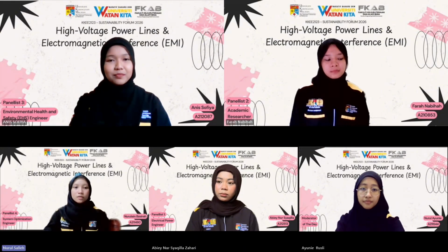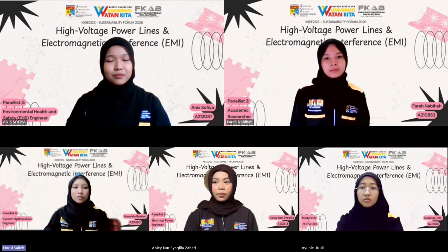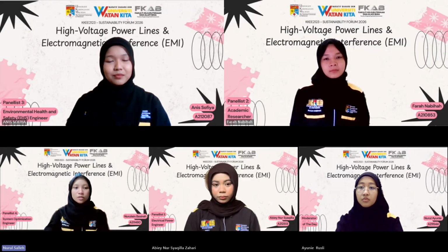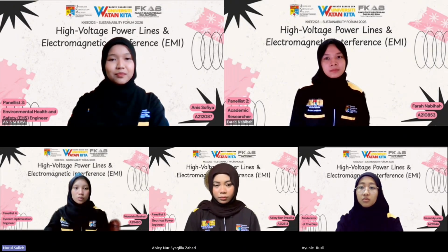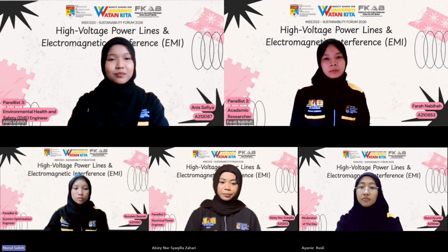First, to eliminate the severe risk of protection relay false tripping or failure to detect actual faults, we must upgrade our substation microprocessors with advanced smart digital signal filters. These filters automatically isolate the main power frequency and completely reject high-frequency electromagnetic interference noise. Additionally, traditional copper data lines should be replaced with optical ground wires, because fiber optics transmit data using light. They are naturally immune to electromagnetic fields, completely preventing communication corruption.